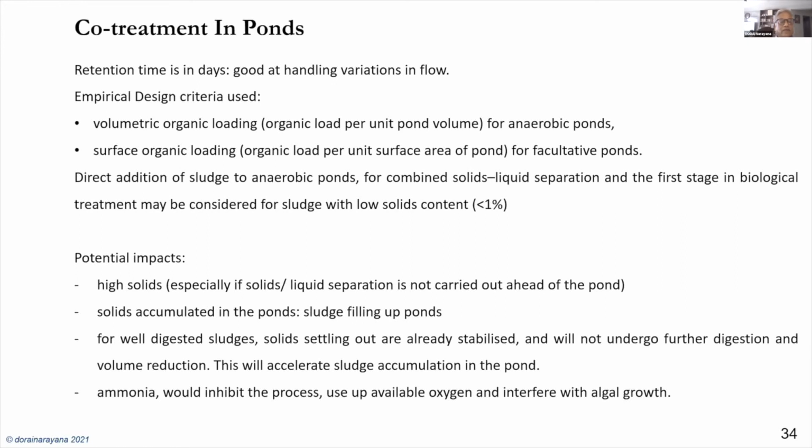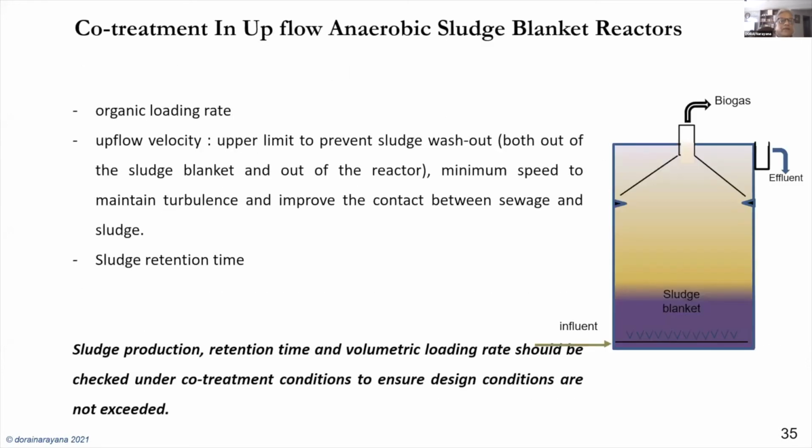And the potential impacts, we need to also check that the volumetric organic loading rate for the anaerobic pond, and the surface loading rate for your facultative ponds, are within limits. These are criteria not to be exceeded. And the volume reduction caused by sludge accumulation could also impact the treatment in the pond itself, right?